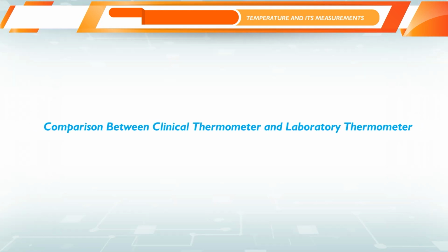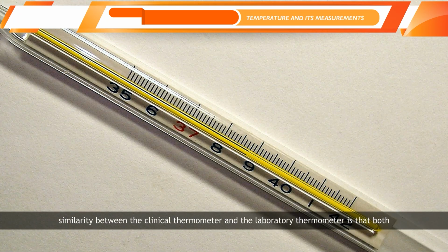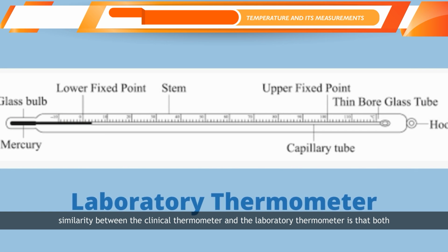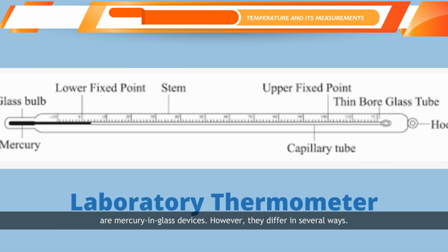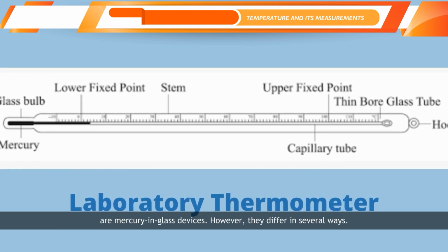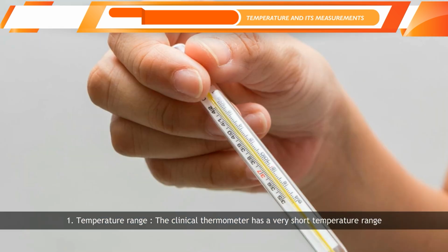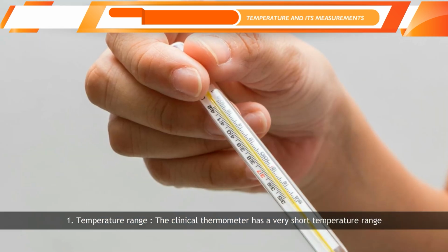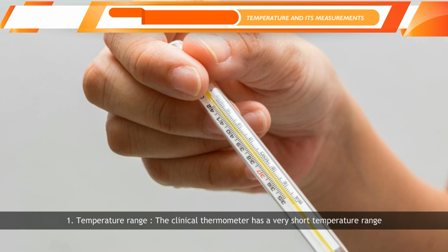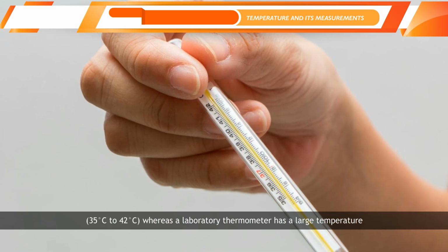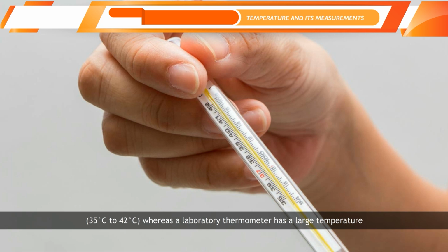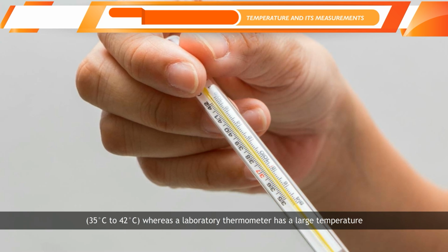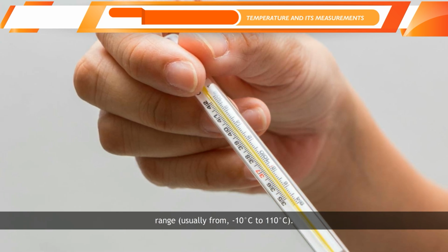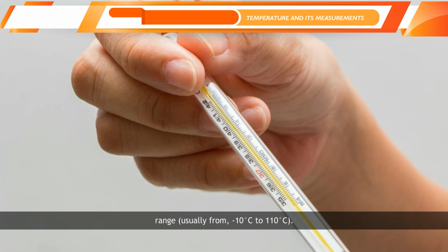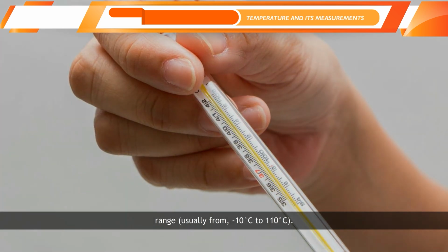Comparison between clinical thermometer and laboratory thermometer. A similarity between the clinical thermometer and the laboratory thermometer is that both are mercury in glass devices. However, they differ in several ways. 1. Temperature range. The clinical thermometer has a very short temperature range, 35 degrees Celsius to 42 degrees Celsius, whereas a laboratory thermometer has a large temperature range, usually from -10 degrees Celsius to 110 degrees Celsius.